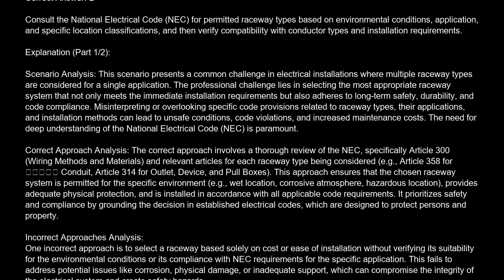Correct approach analysis. The correct approach involves a thorough review of the NEC, specifically Article 300, wiring methods and materials, and relevant articles for each raceway type being considered, e.g., Article 358 for electrical metallic tubing, Article 314 for outlet, device, and pull boxes. This approach ensures that the chosen raceway system is permitted for the specific environment, e.g., wet location, corrosive atmosphere, hazardous location, provides adequate physical protection, and is installed in accordance with all applicable code requirements. It prioritizes safety and compliance by grounding the decision in established electrical codes, which are designed to protect persons and property.